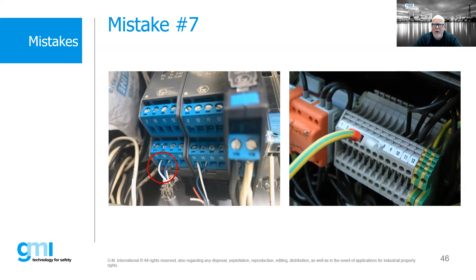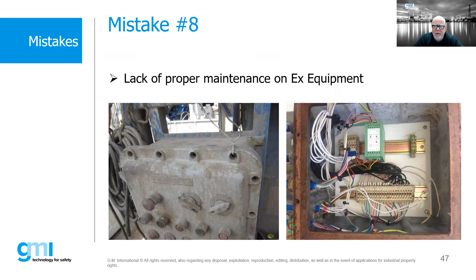The last one: lack of proper maintenance on EX equipment. On the left-hand side, somebody has removed the bolts and used some baling wire to keep the enclosure closed. That is certainly not a safe installation. On the right-hand side, we see corrosion on the flanges of a flame-proof box. We need to be very cognizant of that, because the flanges of a flame-proof box are actually a flame path. When those flame paths get damaged, that means we potentially have a very dangerous situation, so we need to maintain our equipment.